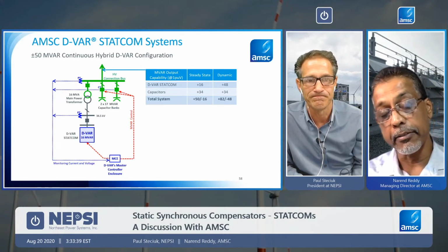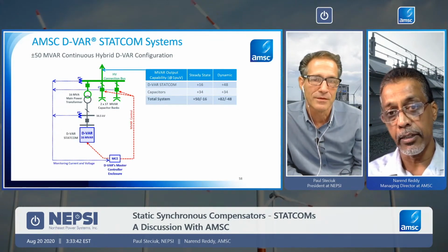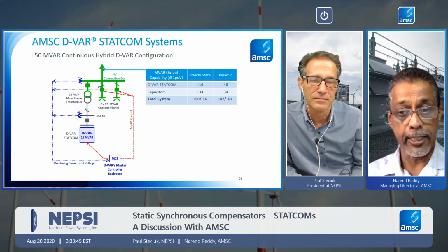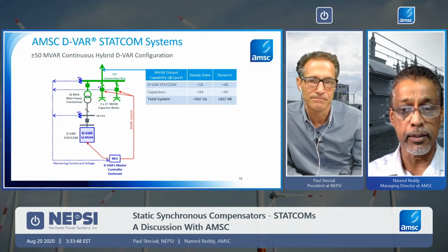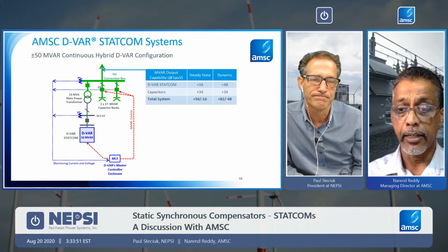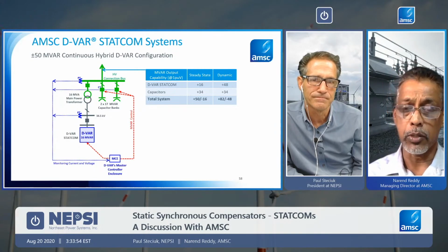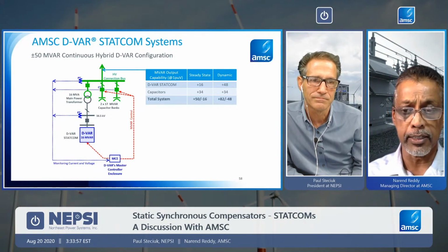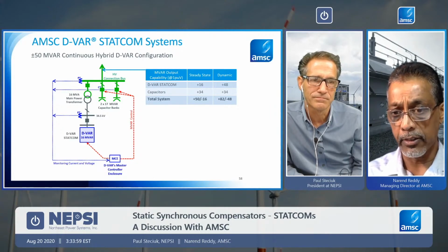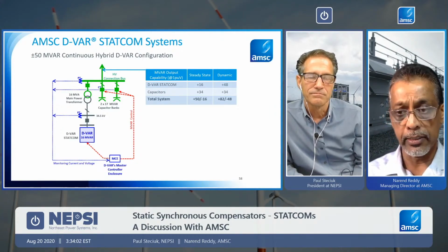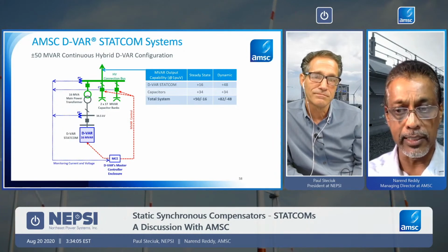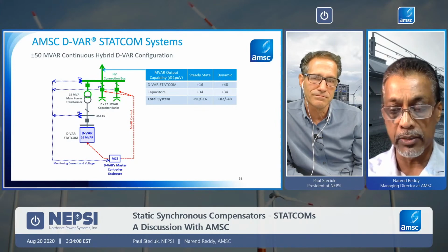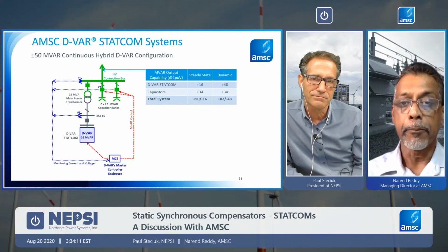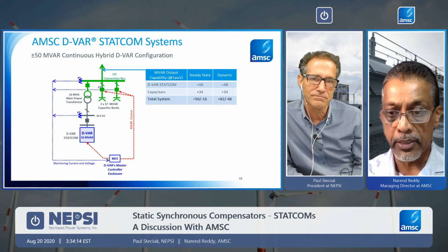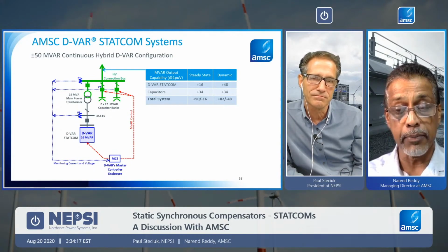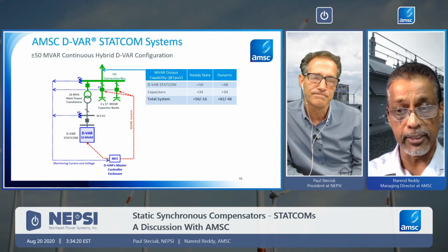Absolutely. And one of the other points that I would make is that, as you mentioned earlier, you also provide fast discharge capability in these cap banks, which may allow them to be switched quickly if needed. The question when switching in capacitor banks or any var is, you're responding to an event or a requirement in the grid. Is that requirement going to be sustained, or is it short term, and then you needed those vars but you don't need them anymore? Now, if you have these capacitor banks multi-step, but also have some fast discharge capability embedded in them, now you're making the system really flexible from that perspective.